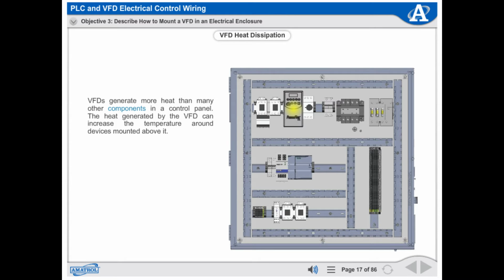VFDs generate more heat than many other components in a control panel. The heat generated by the VFD can increase the temperature around devices mounted above it. It is good practice to install VFDs near the top of the electrical panel as shown. This helps to provide proper cooling for all panel devices.